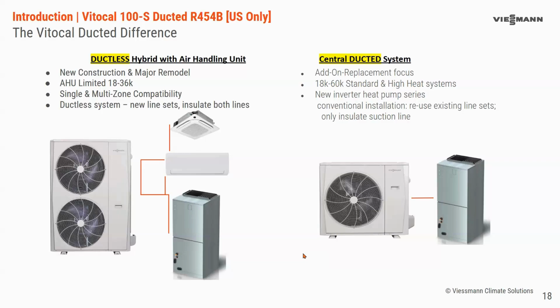But we went over the air handler for ductless and ducted, and what are the differences? The difference is really with a ductless system, unless you're doing a one-to-one, you're limited to 36,000 BTU other than the light commercial applications. In a multi-zone, you can only have up to 2 air handlers, and that allows you no more other indoor units. So you can have a mix of ductless and ducted, which is a benefit of the ductless. However, you're not able to go above 3 tons of ducted.